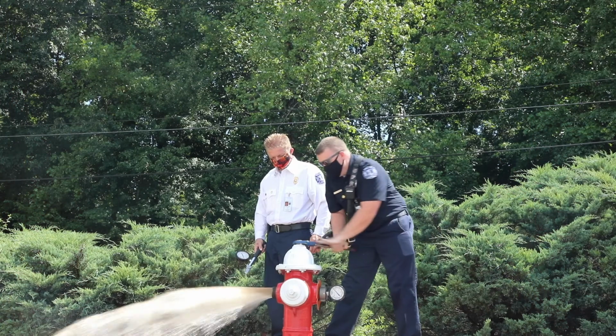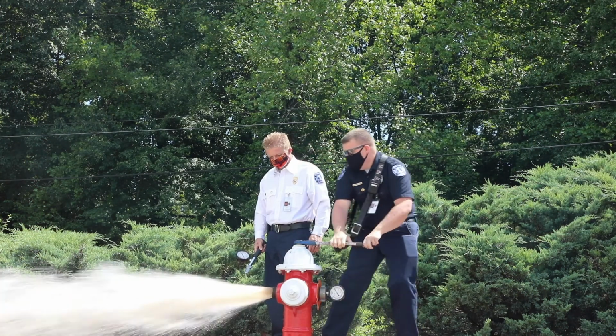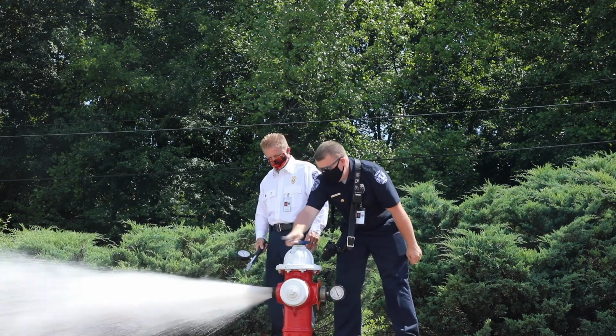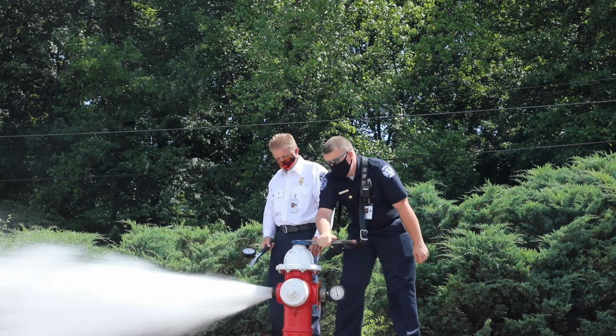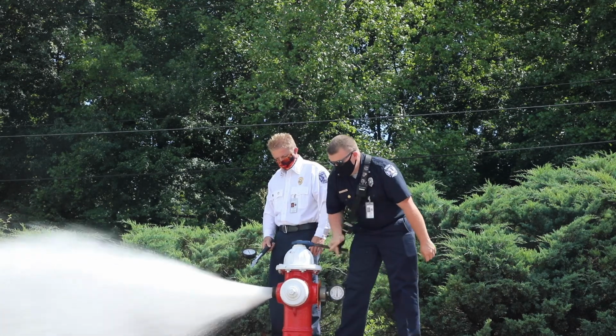Currently, we have to test the water lines and fire hydrants to find out how much water is available. We do this by performing a fire flow test of the nearest fire hydrants. With regular testing, we know the hydrants on Main Street usually provide between 800 and 900 gallons per minute. This does not meet the gallons per minute required for a fire with 100% involvement. However, we usually don't have building fires with 100% involvement. But in downtown areas, our likelihood for a fire to grow or spread is more likely to happen.